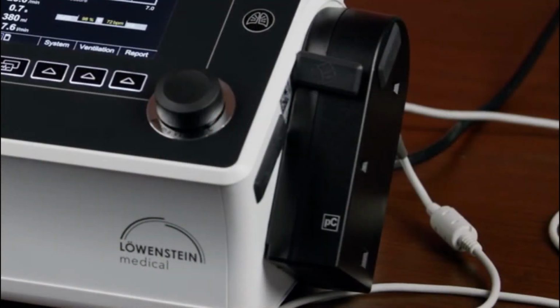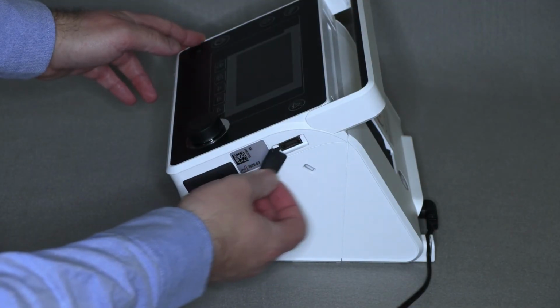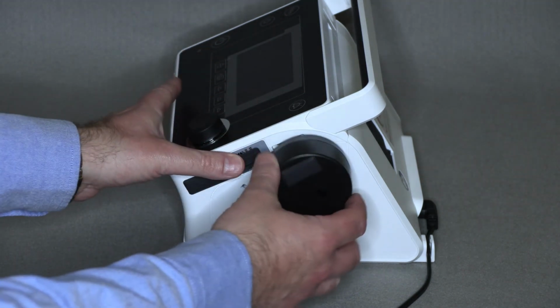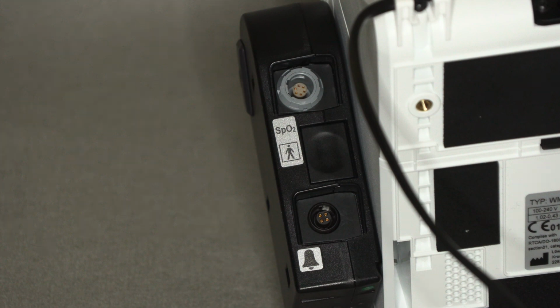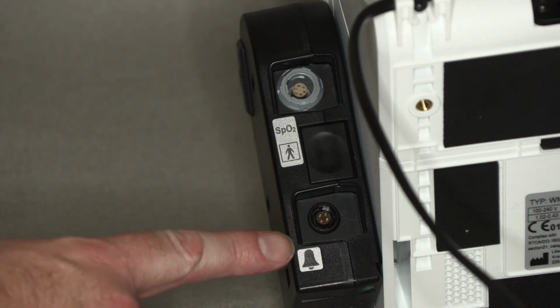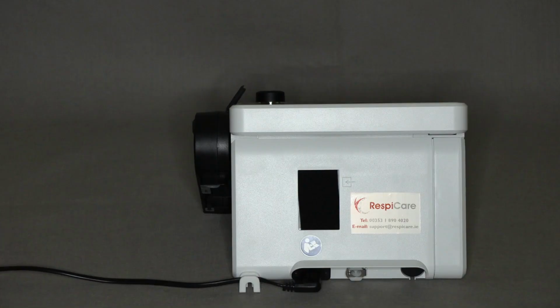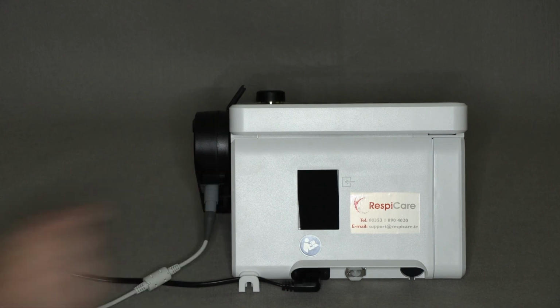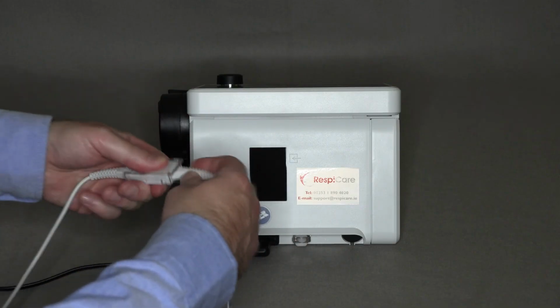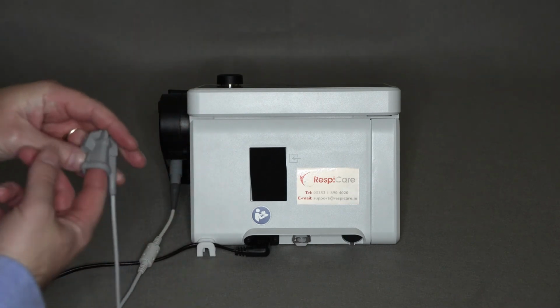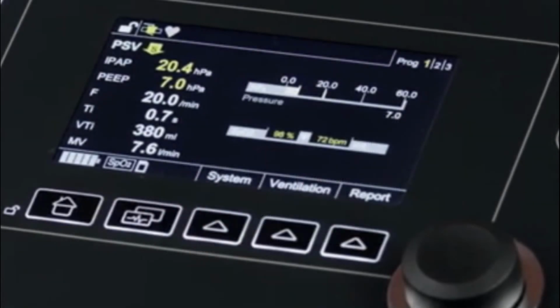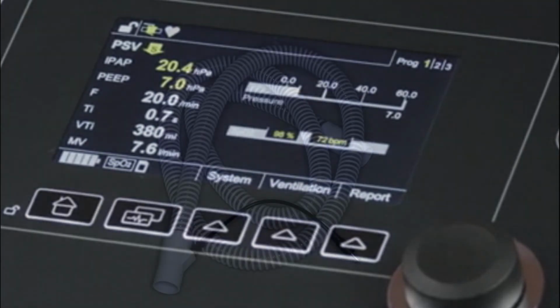The optional prismaCheck module can be used to measure SpO2 and to connect a nurse call system. Pull away the top rubber door from the side of the device and connect prismaCheck. At the back of this optional accessory, you can see where the SpO2 and nurse call adapters would be connected. To connect SpO2, connect the SpO2 connection cable to the prismaCheck and then connect the finger sensor to the end of the connection cable. Once the finger sensor has been applied, the user's SpO2 and heart rate can be seen on the screen when therapy is running. In the alarm settings, alarms can be set to warn of excessive or insufficient SpO2 or pulse.